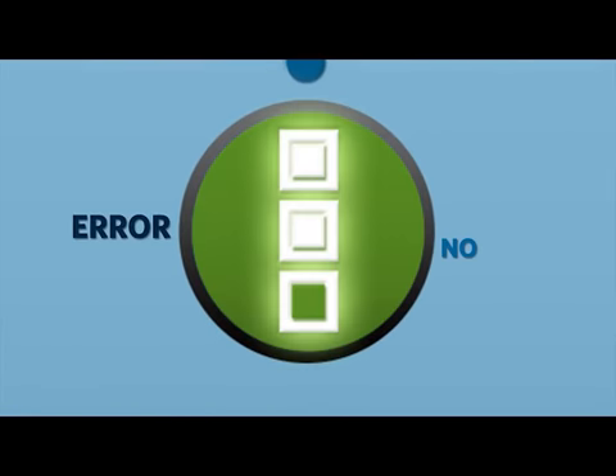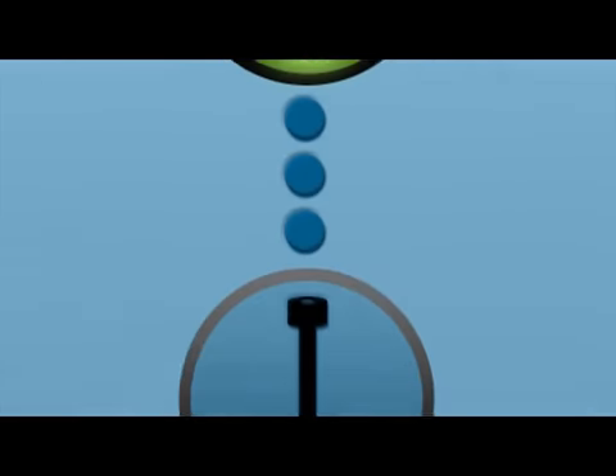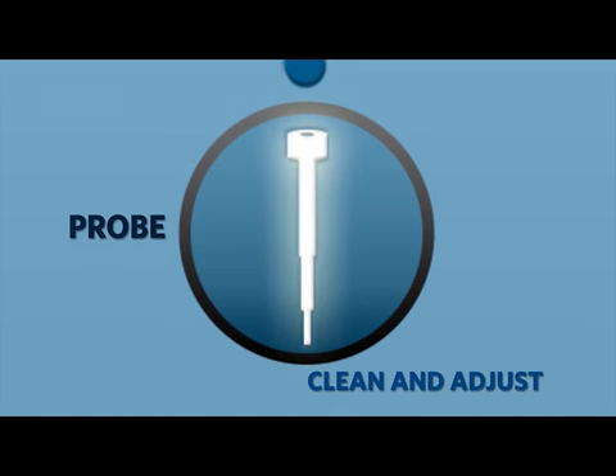But there's one additional step that can be taken to self-resolve issues with your MagPix instrument. Cleaning the sample probe is the last step in basic troubleshooting. It includes sonicating and/or flushing the sample probe, adjusting the sample probe height, then running a system clean. This step requires a calibration verification once completed.